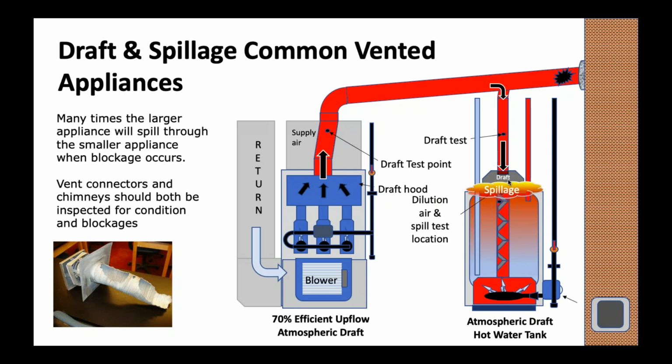So people will check these appliances and think everything's working fine, and it looks like everything's working well, but they're actually dumping all the flue gases for the large appliance out the draft hood on the smaller appliance. It's so critical that when that furnace is running, you walk over to that hot water tank at the common vent and make sure that you're not venting out that hood.